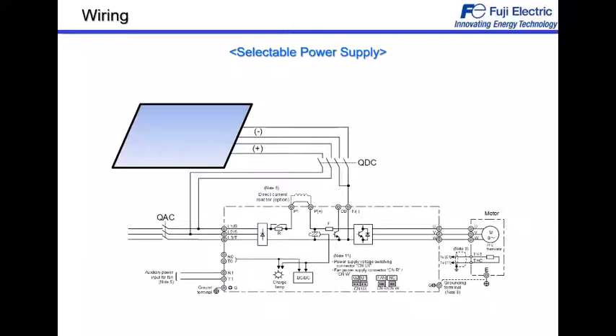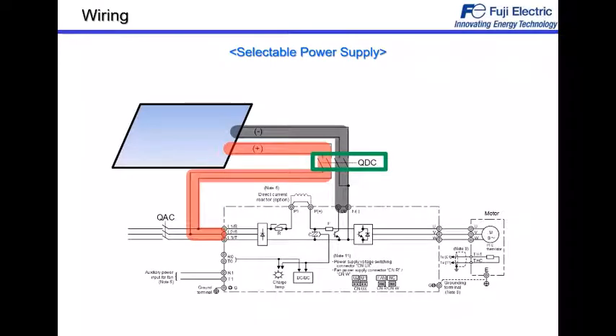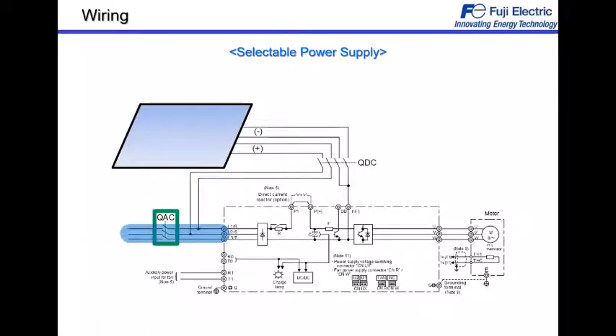Second system, selectable power supply, wiring, same. We have the positive at the entrance of the inverter, and we have the negative in the DC bus. Here we have a switch in order to select if we want DC coming from the panels or if we want AC coming from a generator or from the grid. Here we have the entrance when it's coming from the generator or from the grid, AC power, one or the other.